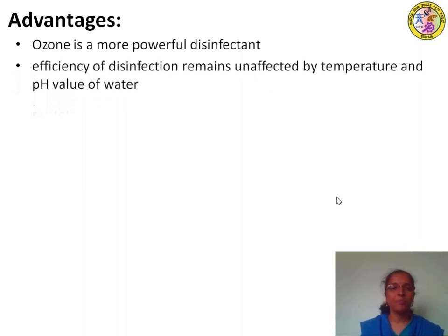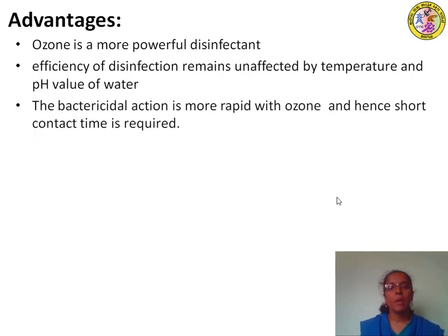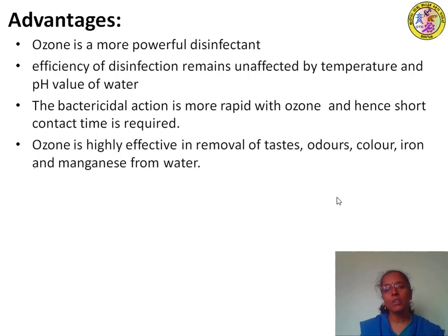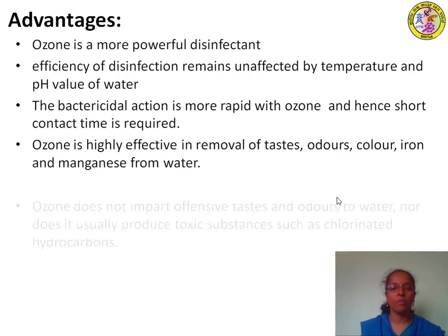The advantages of treating using ozone are, ozone is a powerful disinfectant. Its efficiency remains unaffected by the temperature as well as pH of water. That means the temperature and pH value will not affect the disinfection process using ozone. The bactericidal action is more rapid with ozone, and hence a shorter contact time is required. It is highly effective in removal of taste and odors, color, iron and manganese from the water.